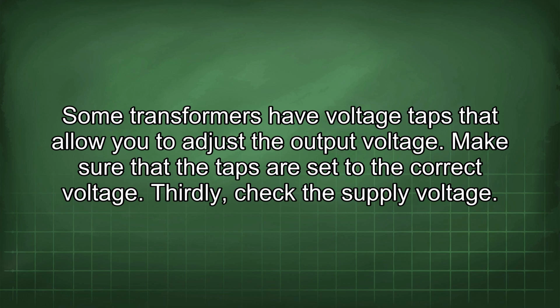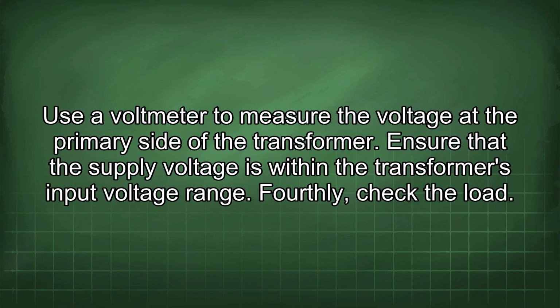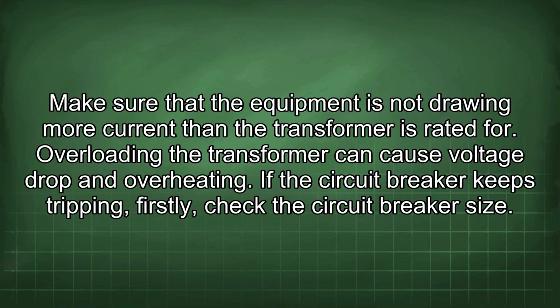Thirdly, check the supply voltage. Use a voltmeter to measure the voltage at the primary side of the transformer. Ensure that the supply voltage is within the transformer's input voltage range. Fourthly, check the load. Make sure that the equipment is not drawing more current than the transformer is rated for. Overloading the transformer can cause voltage drop and overheating.